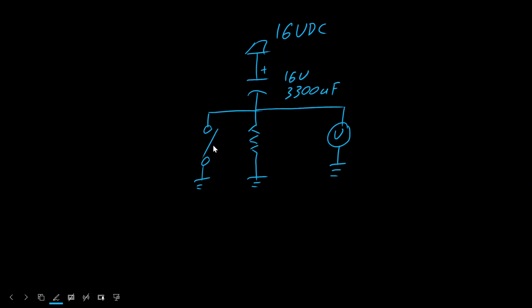We're going to close the switch and wait a couple of minutes. That will allow the capacitor to charge, and it'll also aid a bit in forming if that particular capacitor hasn't been used in some time. When we're ready, we'll open the switch, and then we'll look at the voltage.